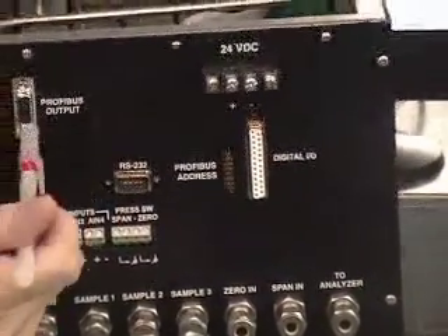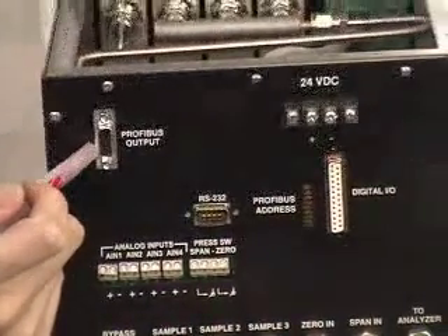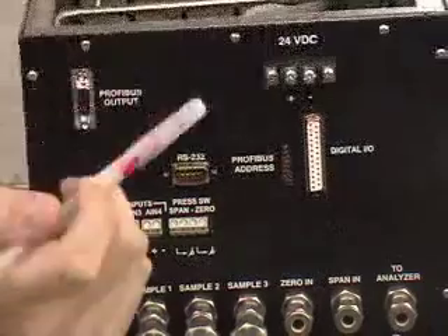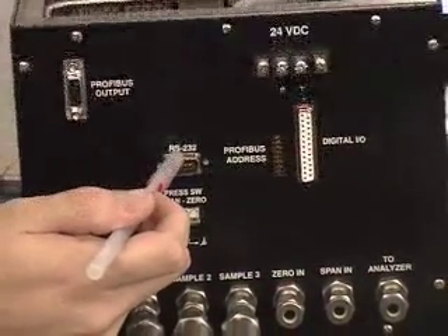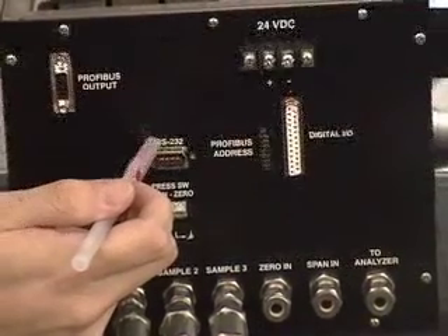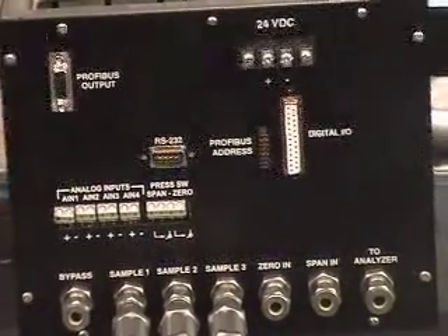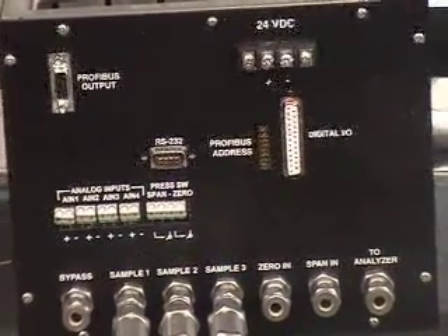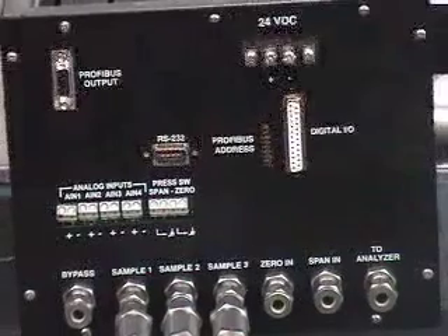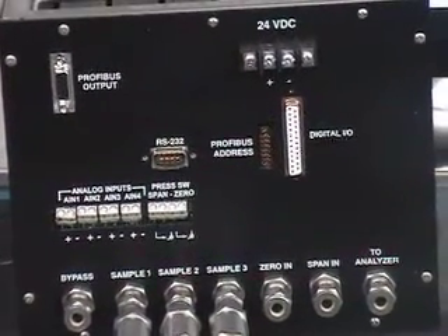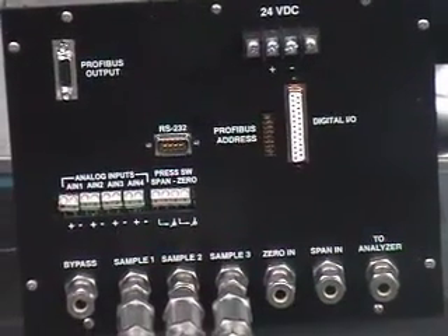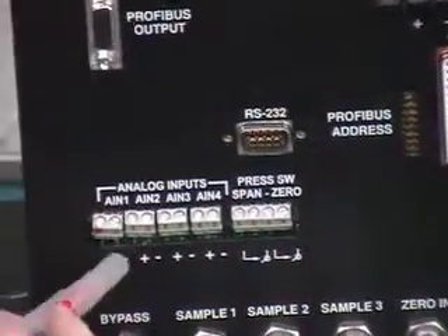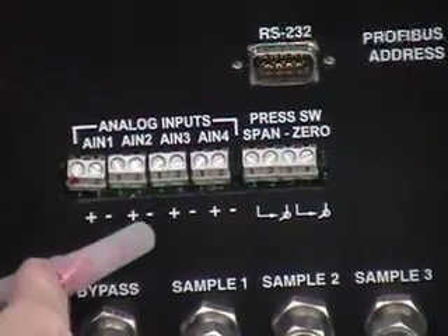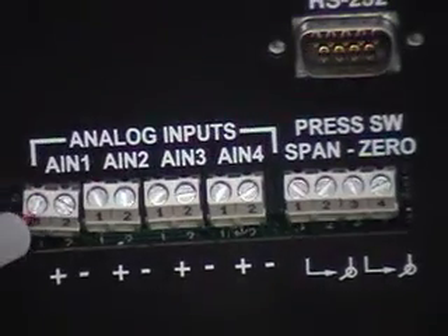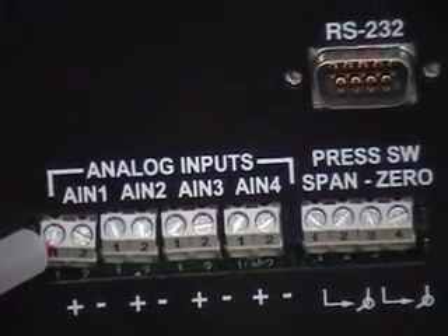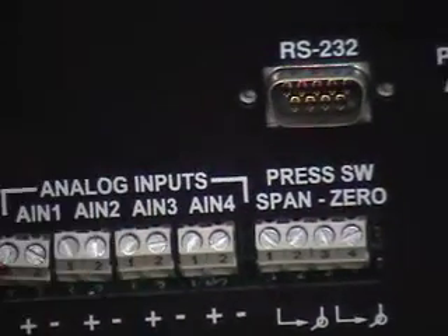Okay, so what do we need? We've got a Profibus output to connect to a PLC or to some Profibus network. We've got an RS-232 input from an analyzer that is RS-232 ready. In this case, it's a 3000 TA oxygen analyzer that we are going to connect to. If we have an analyzer that doesn't have RS-232 and that has the same protocols as a 3000 TA analyzer, then we can connect the 4 to 20 milliamp from another analyzer to one of these analog inputs. We've got 4 analog inputs, of which we use one for the 4 to 20 milliamp input from one analyzer. We can connect here and monitor the 4 to 20 milliamp and transmit it through the Profibus network.